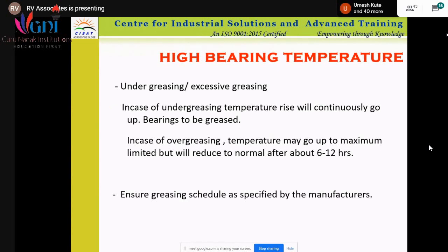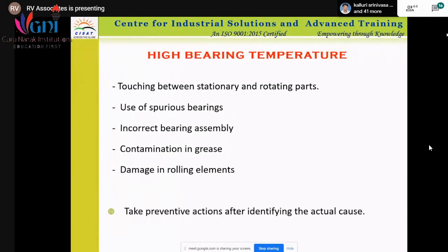Then the quality of the oil or greasing. Do note that heavy greasing as well as low greasing are both dangerous. Greasing should always be done properly, as mentioned by the OEM, the original equipment manufacturer. So all the guidelines prescribed by the OEM should be followed. These are more of the reasons for rise in temperature.